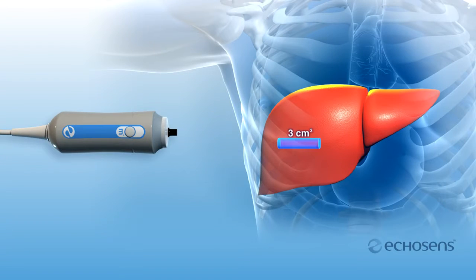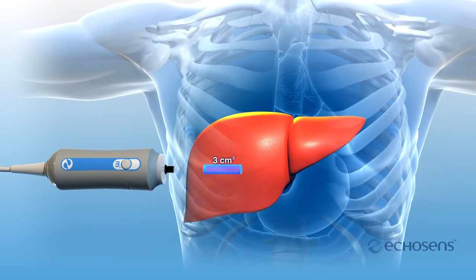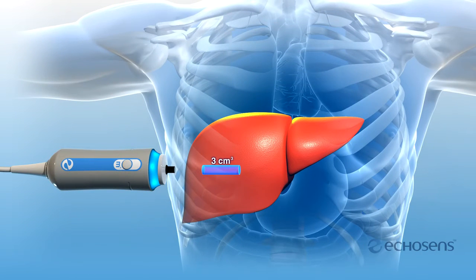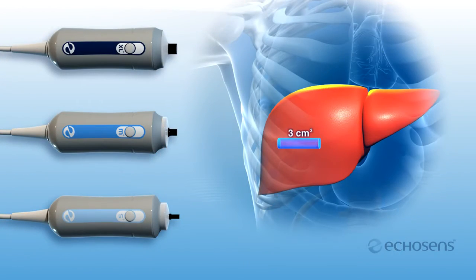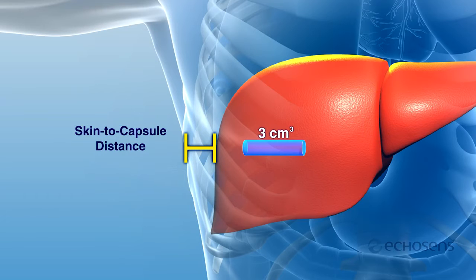FibroScan adult probes examine a 3 cubic centimeter cylinder of the patient's liver. This large examination volume, more than 100 times the volume of a biopsy, helps to minimize sampling error. Using the correct probe model based on the adult patient's skin-to-capsule distance is required by the test protocol.